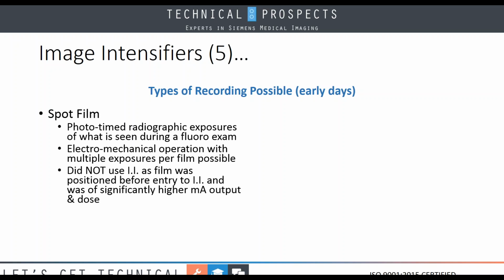Basically, what we did here is at the quick turn of a handle, our generator stopped the fluoro operation, converted to a radiographic operation, and was going to generate a high MA shot across our patient to expose a piece of film. We had a piece of film back in the tray that we would then bring forward into the beam. We would collimate down based on the programming of anywhere from 1-on-1 to 16-on-1 exposures on a piece of film. And we would collimate and put our image on the piece of film, making a radiograph that had to be photo timed because we didn't know where in the body it was going to be required, so that we could get a good quality image, as we only got one shot to get this correct.